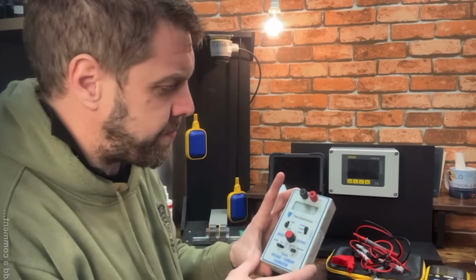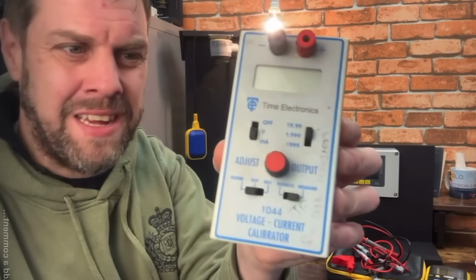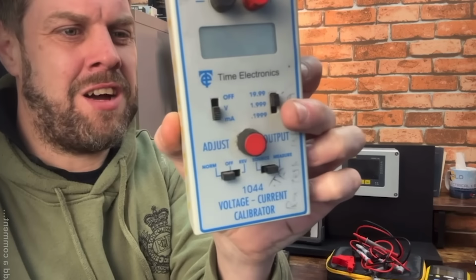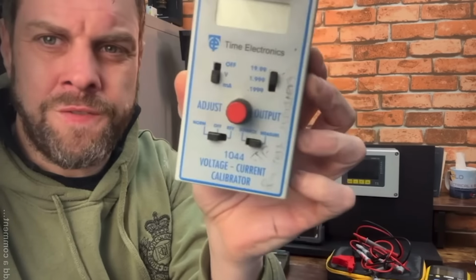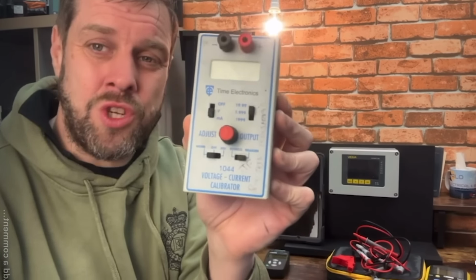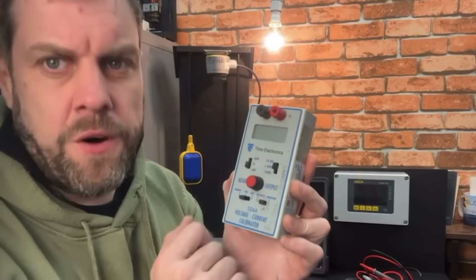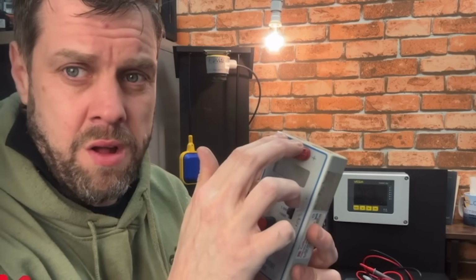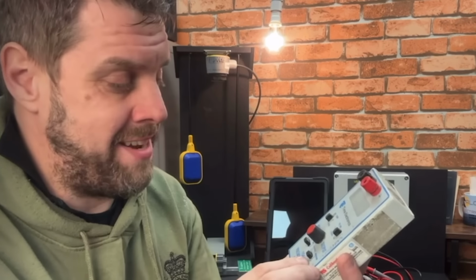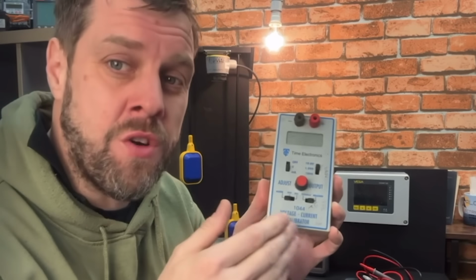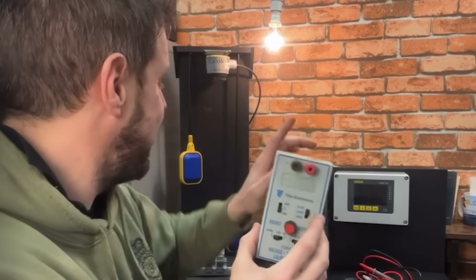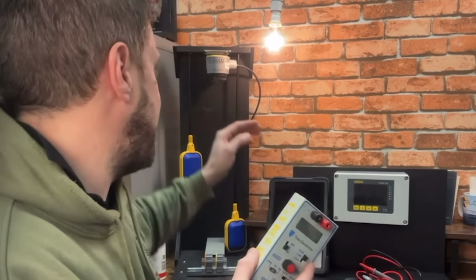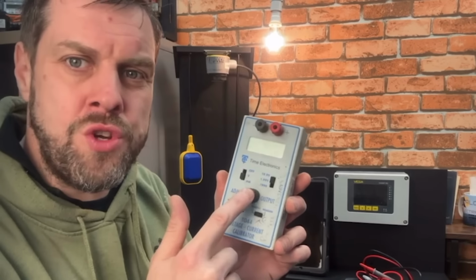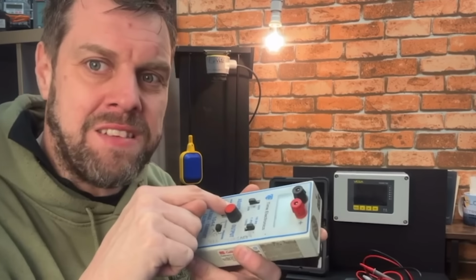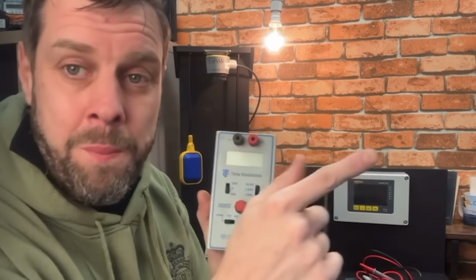First of all, I'm going to show you this one. This is a Time Electronics 1044 voltage and current calibrator. This will do 2 things: it will measure 4 to 20 milliamps, so if you put a signal in it, it'll measure it. It'll also source it, so it'll make 4 to 20 milliamps. So if you've got something that accepts 4 to 20 milliamps, this can pretend to be that sensor. For example, if depending on the height of a sensor a motor ran faster or slower, and you didn't have a sensor, you could use this to inject the signal. This will make 0 to 20 milliamps by turning this pot and pump it into something.